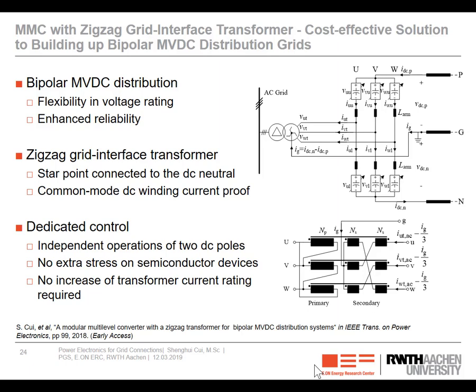And for this zigzag transformer, when we connect the windings in a dedicated way, even if a DC current flows into the neutral point, the transformer will never saturate. It's quite different from the normal transformer, because for a normal Y-connected transformer, as long as a certain amount of DC current flows through the winding, the transformer immediately saturates. But here, with such a connection, it is possible to have DC current flow. It means that this current and this current can be different. Or in other words, these two poles can operate at different power.